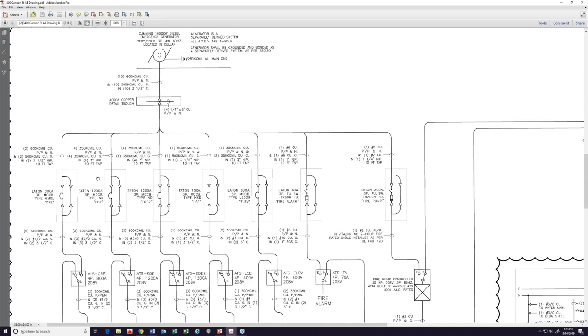Now, the other thing that I'm achieving with this is that I am also complying with 700.10. It used to be 700.9 in the older code version, now it's 700.10, I believe. That requires all these loads to be separated. And a lot of design engineers fail to know that. A lot of people don't realize that, and that's at least how I see that a lot of design engineers don't pay too much attention to code.